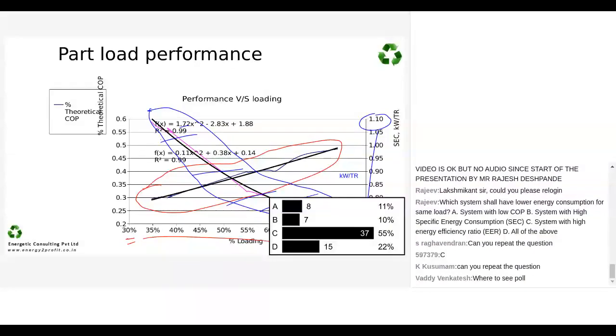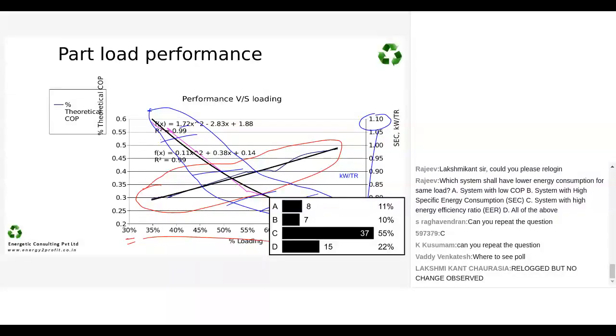So great, 55% of the people feel that it is the option C, that is system with higher energy efficiency ratio will have better performance, which means system which gives higher BTU per hour for the given kilowatt will be a system with lower energy consumption. The answer is absolutely perfect. A, B, and D are wrong answers. Which means people who have voted for A, system COP when it is low, you are actually consuming more energy per ton. When the system specific energy consumption is high, means that we have higher kilowatt for same TR output. It cannot be lower energy. So guys, good that 55% of the people got it right, and maybe 22% of the people got tricked by all of the above. So please be careful on that.